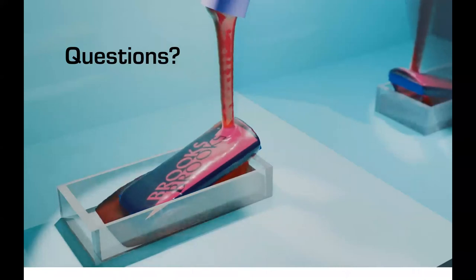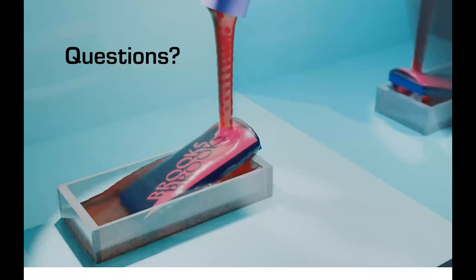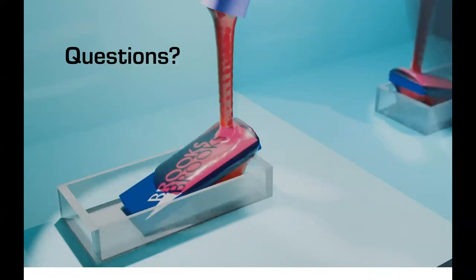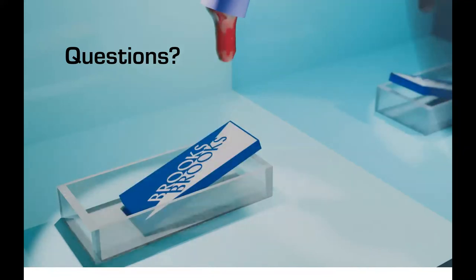A couple of questions: someone asked about the 0.8 factor being a 20% reduction. It's actually 1 divided by 0.8, which is 25% — it depends on how you describe it. On temperature: generally fluids get thicker as they get colder, but there may be exceptions with certain chemicals. Does air added to a fluid lower the viscosity? Probably not the actual fluid viscosity — now you've got a non-homogeneous solution, like sand and water. How small the air bubbles are matters; if they're entrained fine bubbles, the mixture would likely shear more easily.